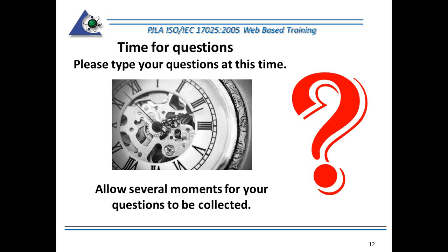Here's a question. What is CMC? Now, this apparently comes from someone not in a calibration laboratory. It's the calibration and measurement capability, which is very quickly and simply an estimate of the best measurement uncertainty that a laboratory is capable of when performing a more or less routine calibration of a nearly ideal device under nearly ideal conditions.